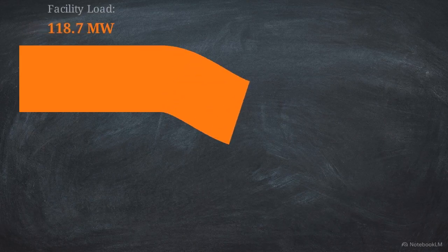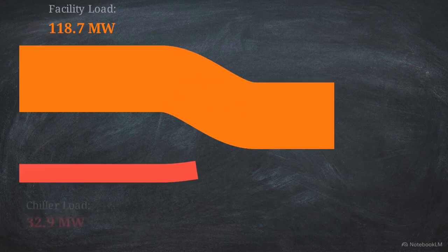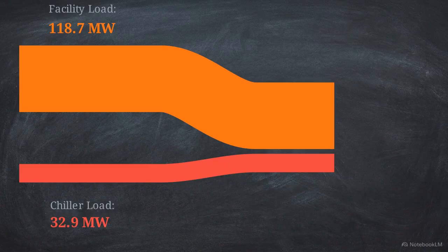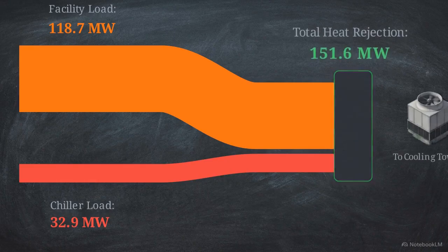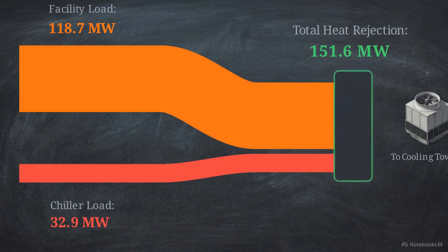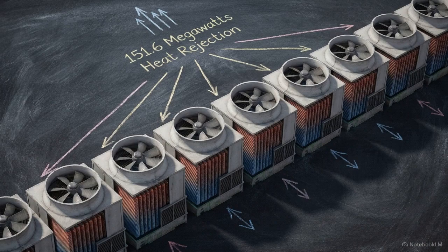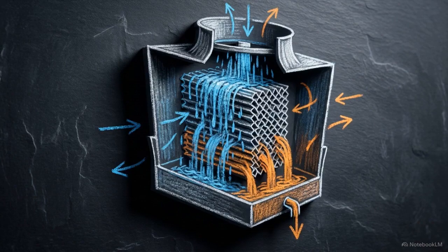This flowchart tracks where the 2 thermal paths converge. Adding the 118.7 megawatt facility load to the 32.9 megawatt chiller load establishes the final thermodynamic boundary, a total heat rejection requirement of 151.6 megawatts. Regardless of internal efficiency, the exterior cooling towers must be sized to reject exactly 151.6 megawatts to the sky. The baseline method for rejection is the open-circuit wet cooling tower.